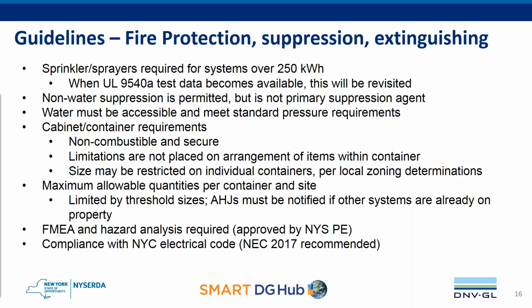For fire protection, suppression, and extinguishing, there will be a requirement for sprinklers or sprayers over 250 kWh. And when UL 9540A test data becomes available, there may be an opportunity, depending on the outcome of those tests, to determine the flexibility within that requirement. Although non-water suppression is permitted, such as a Novec system, it's not allowed as the primary suppression agent unless testing demonstrates that it is as effective as water. As such, water has to be accessible on site and meet standard pressure requirements. So that can be determined by a hydraulic engineer.